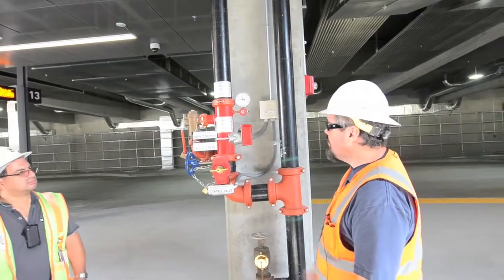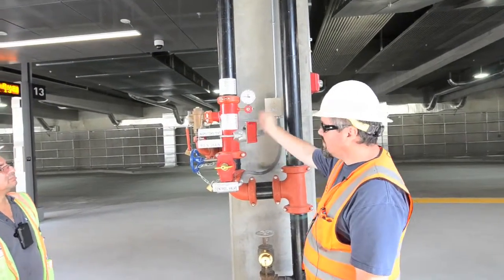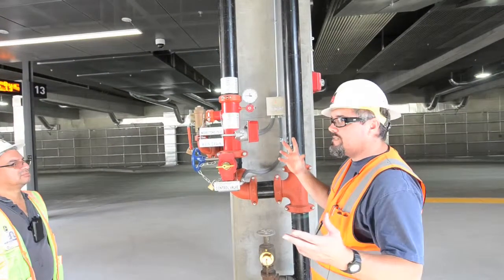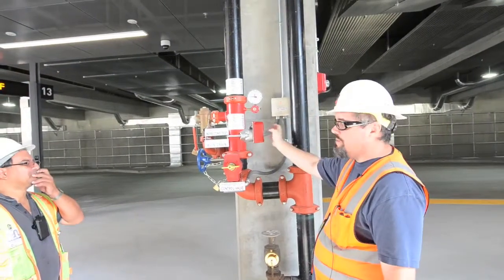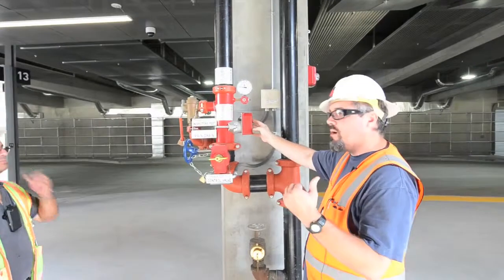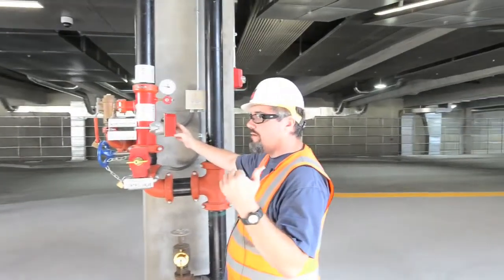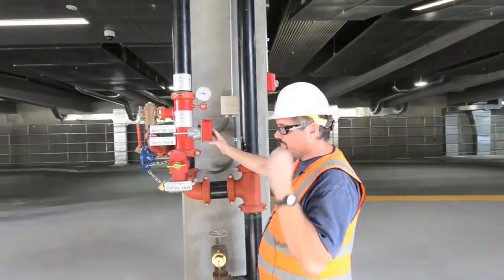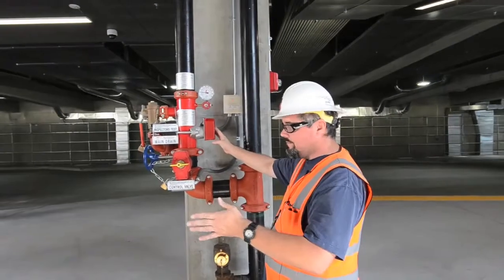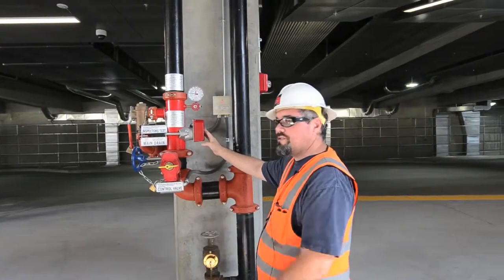And right now, here's the flow. That just checks the water flow, because if a sprinkler busts open, the water flows, and this will make the alarm go off. Up there it will say water flow, and then the bells on the building will go off. That's for the fire department to hear what section of the site they'll rush to first.